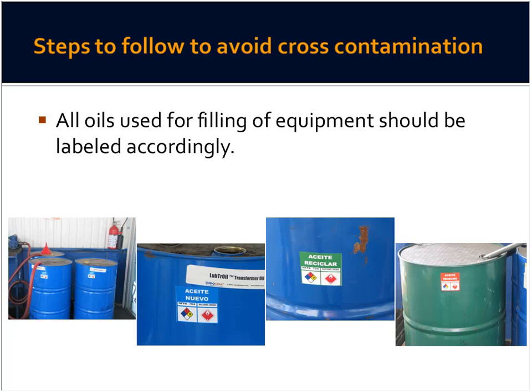In some countries there is a regenerating process for oils, which extracts humidity, impurities, and soil so the oil can be reused as electrical oil. It's very important that testing is done before including any oil in the regenerating process, so as not to contaminate large volumes of oil that, once regenerated, can be reused without worry. This is something we must keep in mind in the regeneration of oils.